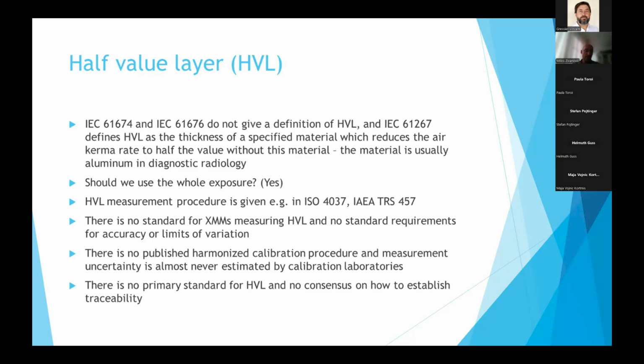In order to have a harmonized definition, we need to decide if we are using the whole exposure for HVL measurement. So for time, I said that we are starting only when air kerma rate first reaches 50% of the maximum value. Here for HVL measurements, we recommend that the whole exposure is used. And of course, if you're using, for example, ionization chambers, you will have to use the whole exposure. So you usually don't have the possibility to remove the first part of the exposure.